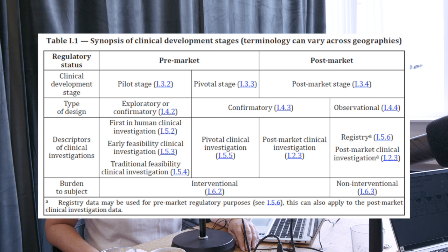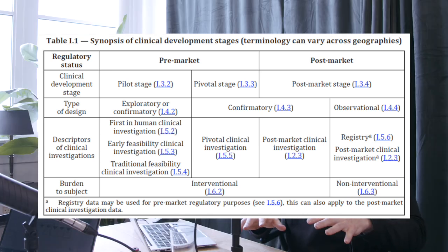Yeah, true. It's really difficult to evaluate without having a specific device, and that's why the plan is so important, because you need to know that. Is there a long history of using this device type? Well, then that is your justification of going directly into a pivotal trial. We see that quite a lot, actually, with devices, that there is a long precedence of using a device type, and then they jump directly to a pivotal study.